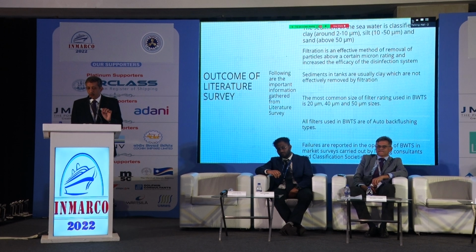If you're expecting 2 to 10 micron and your water meets a 50 micron strainer, would you expect this to be removed from the water? Answer would be no. Remember, the entire ballast water treatment system is designed for a biological process. Now this has nothing to do with biology. This is to do with the physical process, because as engineers we have been facing a problem which is physical in nature, that is choking of the filter.